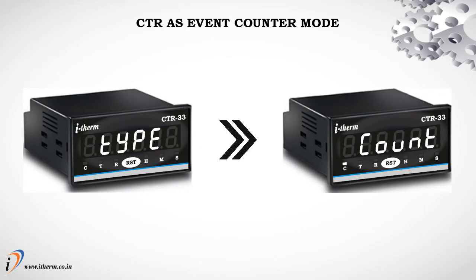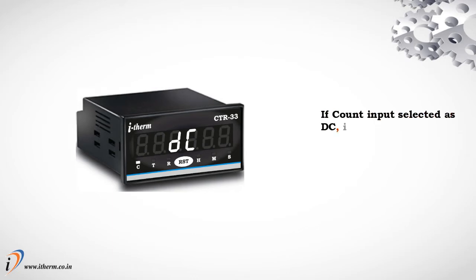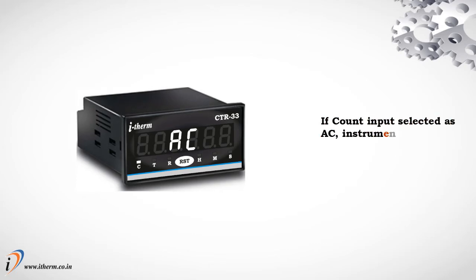CTR as event counter mode. Parameter 2: Count input type. By this parameter, the user can select between AC or DC as count input. If count input is selected as DC, the instrument will count pulses from a proximity sensor or by potential-free contact. If count input is selected as AC, the instrument will count pulses from a 230 volt AC supply.